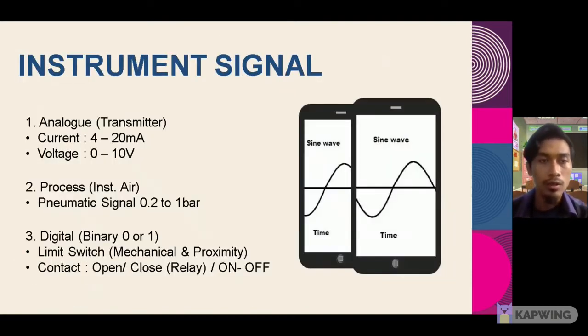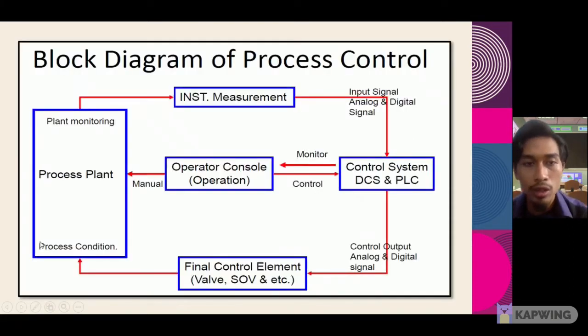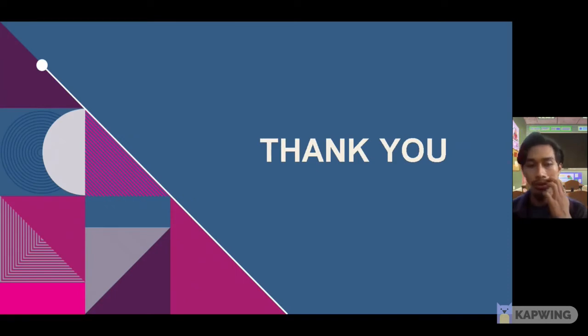So for the instrument signal, for the analog transmitter, the current is 4 to 20 milliampere, and for the voltage, 0 to 10 volt. For the process, it is a pneumatic signal, and for the digital, it is limit switch, contact open close, relay on off. So this is a block diagram of process control. You can see from the process plant to the instrument measurement. The input signal goes to the control system, DCS and PLC, goes to the monitor, operator console or control output analog, to the final control element, and goes back to the process plant. That's all from me. Thank you.